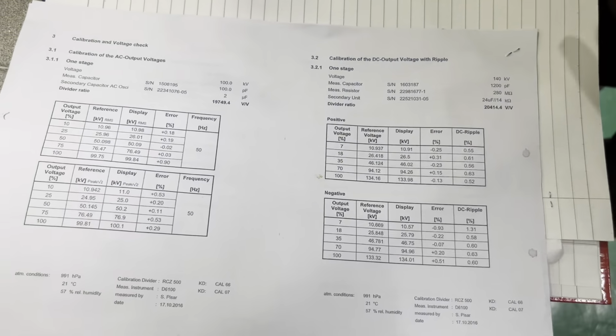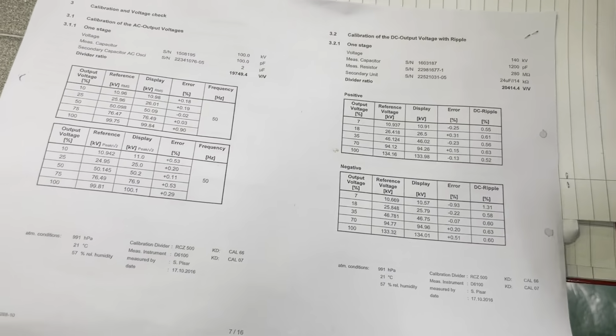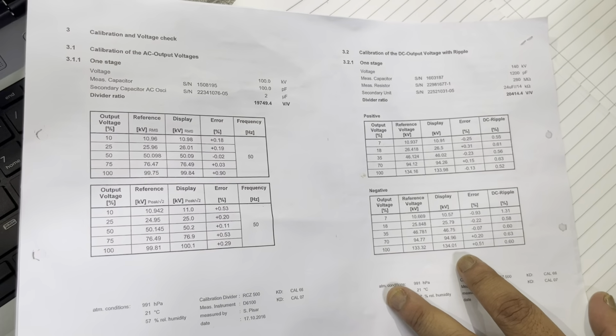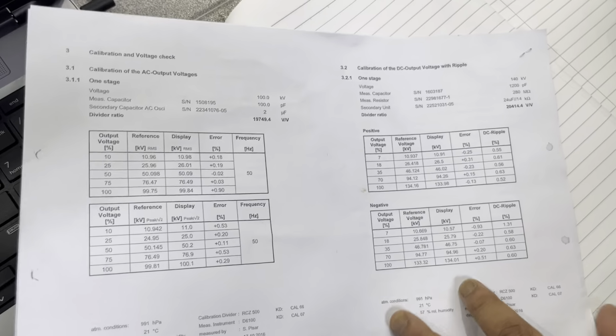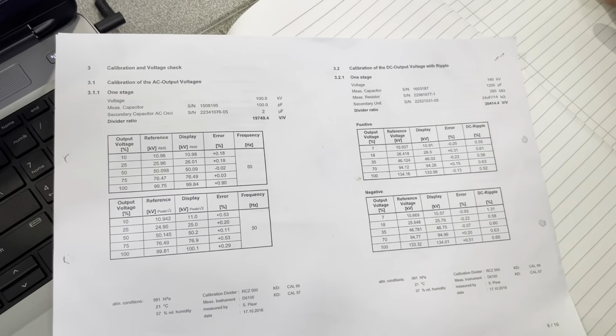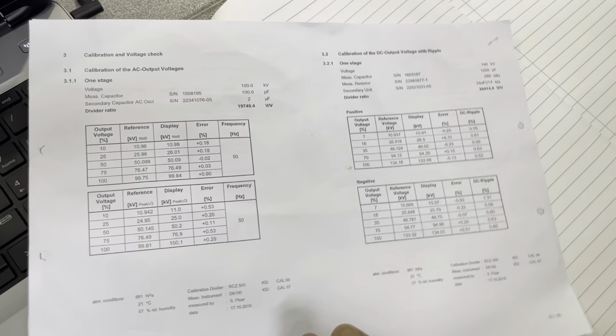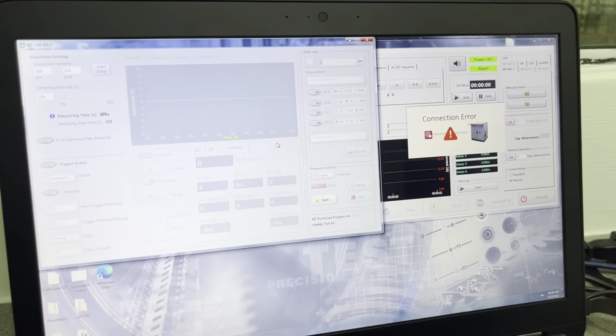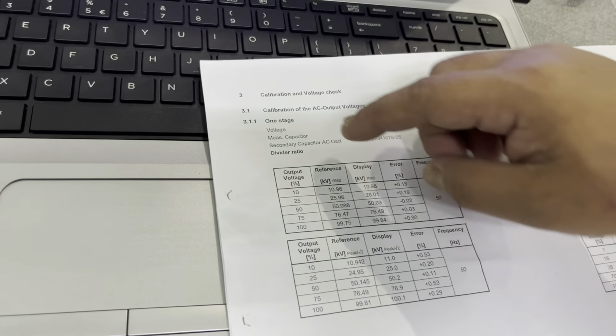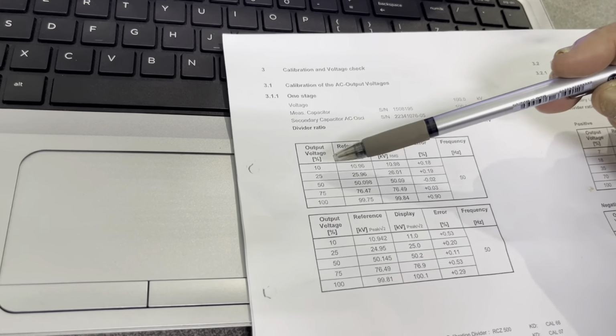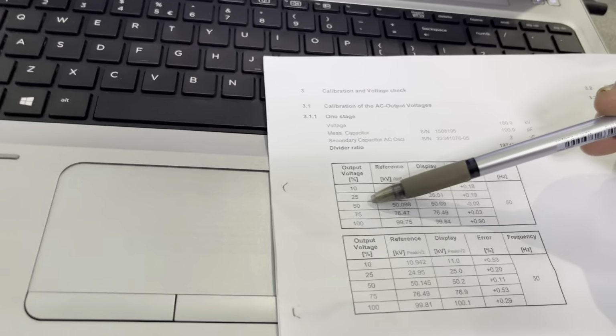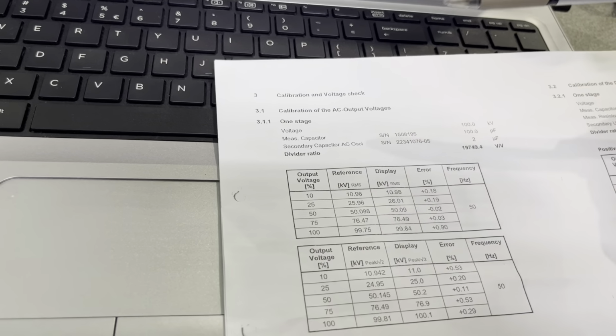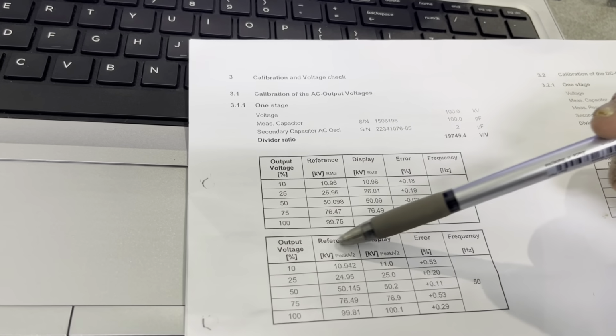Okay, before we start any of our measurement, we have to make sure our system is perfectly calibrated and the error is within our range. Okay, how to do it? One, we are going to refer to this calibration sheet. Okay, we are going to set our output voltage at 10%, 25%, 50%, 75%, and 100%. And this is our reference value.